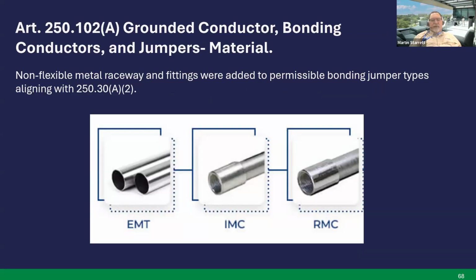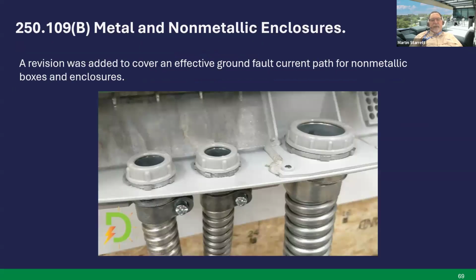Article 250-102A, grounded conductor, bonding conductors, and jumpers, material. Non-flexible metal raceway and fittings were added to permissible bonding jumper types, aligning with Article 250-30A2. So basically, besides a wire type bonding jumper, you can use a non-flexible metal raceway and fittings with this new revision. Next slide.